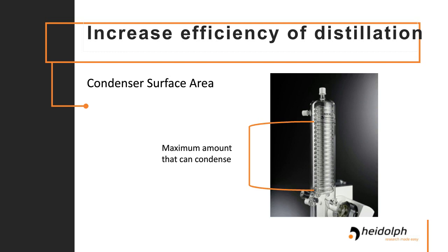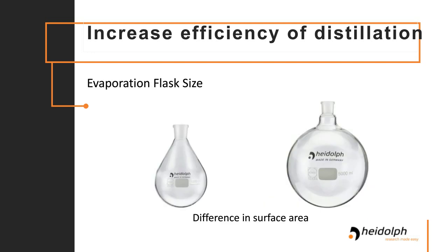The next thing to consider is the size of your evaporating flask. You want to consider how much liquid you want to be evaporating at one time, along with the size of the flask affecting the entire surface area of what you're evaporating. A larger flask leads to more surface area, which means more can be evaporated at the same time. And also, you don't want to go above about a 1/3 fill on your evaporating flask, because above that will also start to reduce the surface area and can lead to some of the liquid bumping into your condenser.